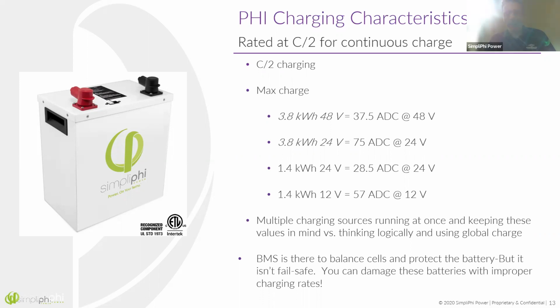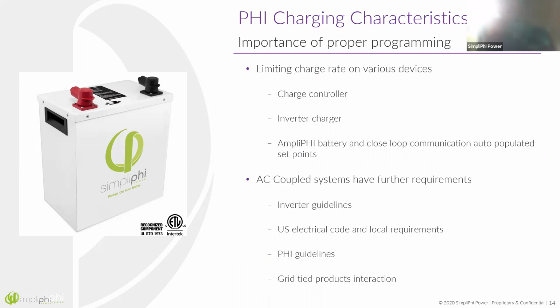The other thing to tell you is, yes, these batteries have battery management systems. But really, this is not a fail-safe. The battery management system is there to protect the battery, but it's really the last line of protection. Proper sizing and proper design of systems is important when we're looking at protecting the battery. The battery management system's main job is to deal with balance of power and keep the battery operating properly. So it's important that we properly program equipment. We want to limit the charge rate on various devices. So if we have a small battery bank that's undersized for our charge controller, we're going to need to make sure that the charge controller is properly programmed.